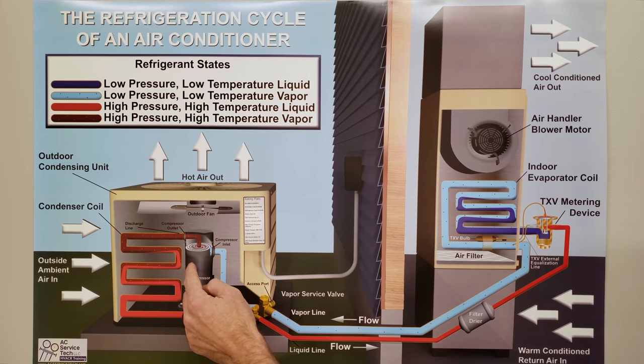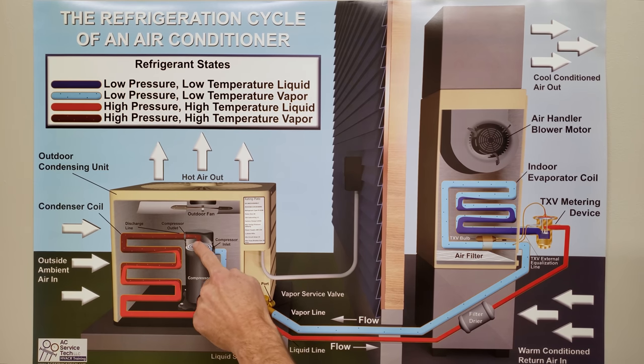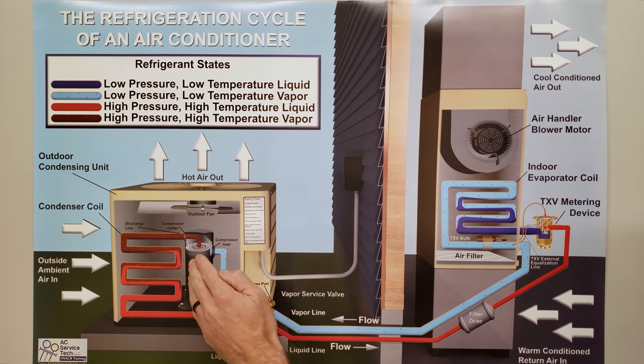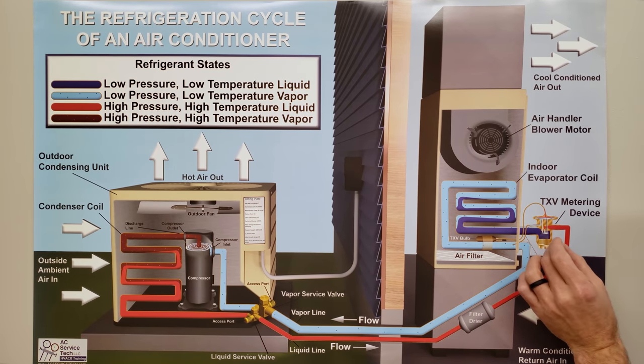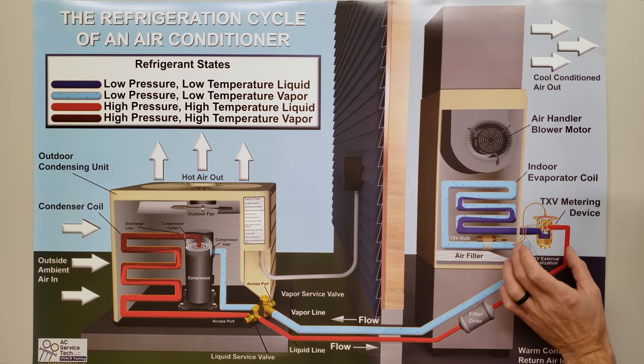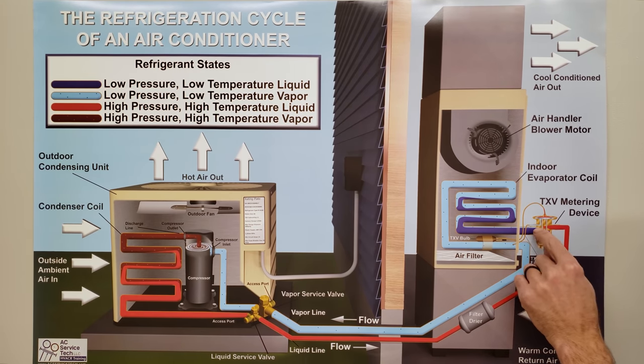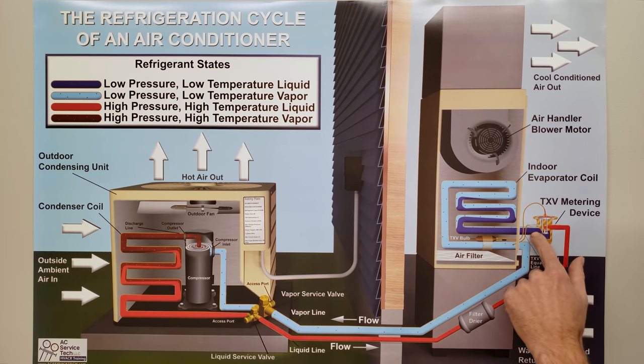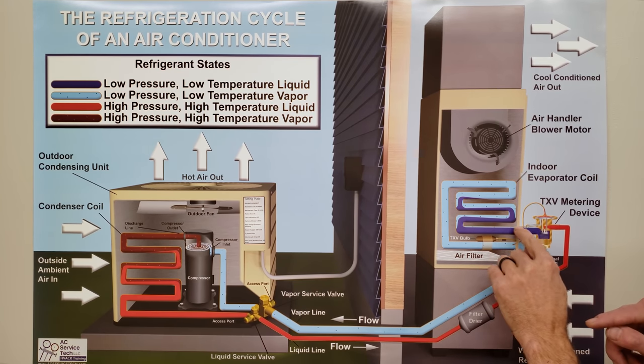You have a couple of devices accomplishing this task. One is the compressor — a pressure-increasing device — which takes low-pressure, low-temperature refrigerant in and outputs high-pressure, high-temperature vapor. Then you have the metering device, a restrictor or pressure-lowering device, where high-pressure liquid enters and low-pressure liquid exits.